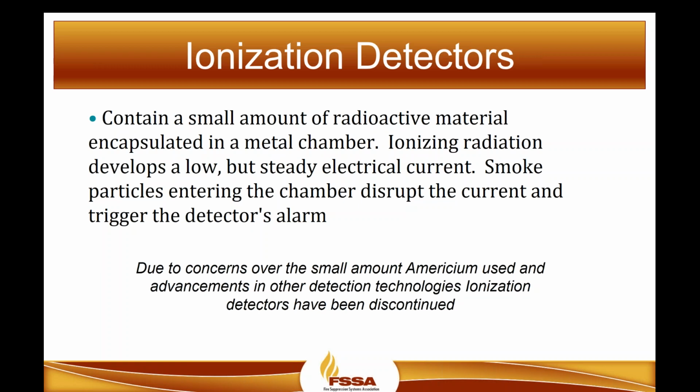Yeah, that's correct, Dan. We've seen a decline in the availability of ionization smoke detection over the past few years. Typically, they were more responsive to a fast flaming fire, and photoelectric was much more susceptible to picking up smoldering fires. But the issues were always there. They were much less effective in high airflow environments such as subfloors or above acoustical ceilings, and would actually cause trouble conditions with excess exhaust or airflow going by them. So, it's been encouraging to see the advances in the photoelectric technologies, and having one particular flavor of detector out there is a lot more advantageous for the designer.